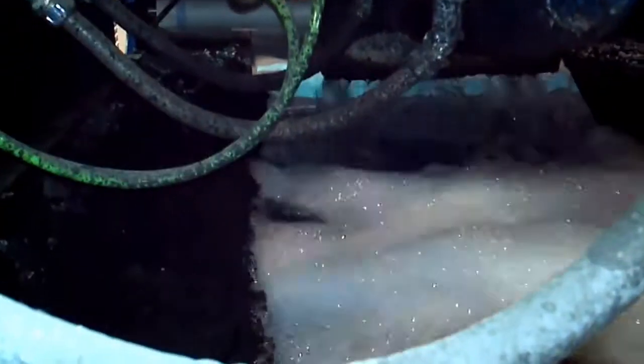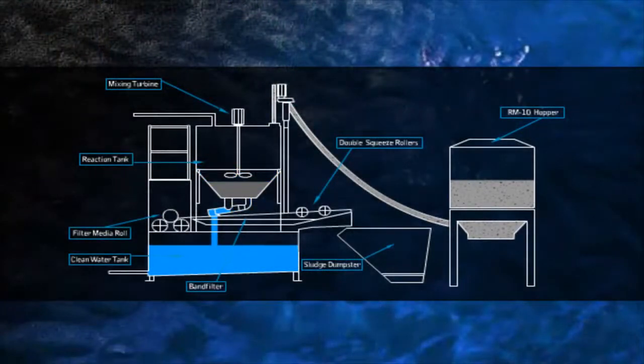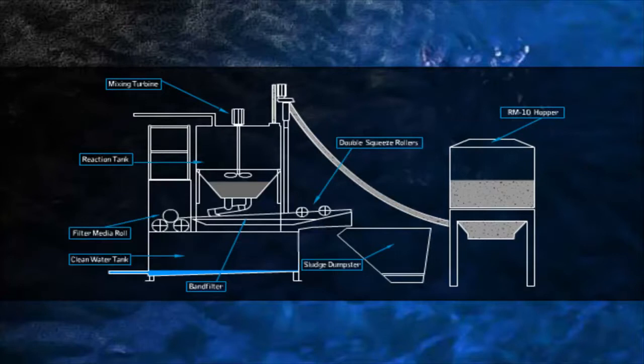After the solids have settled, the clean water valve is opened. Treated water passes through the filter media on the conveyor and into the clean water tank. The filtered water can then be discharged directly into the sewer system or reused in other applications.